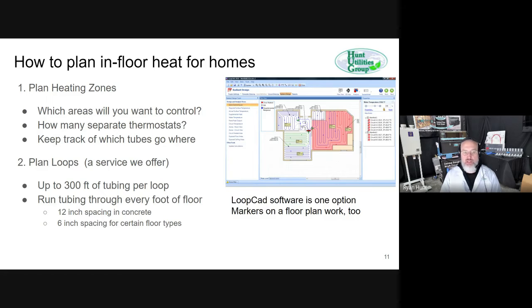When you're planning the loops, use up to 300 feet of tubing, and that's half-inch PEX tubing, which is what we recommend. You run the tubing through every foot of the floor, and in some places, particularly outside, like snow melt applications, it has to be 6-inch spacing. Some people will do 6-inch spacing under wood floors also, particularly with some of the systems I'll show you. To do those loop layouts, you can use LoopCAD software, which is a pretty easy to use system. We offer that as a service for our customers.